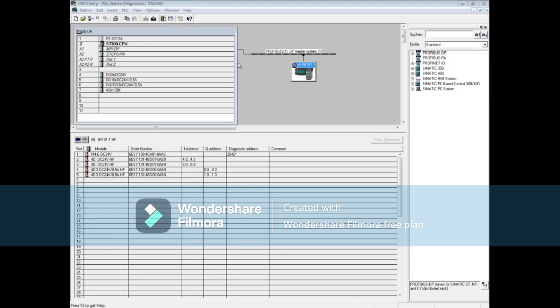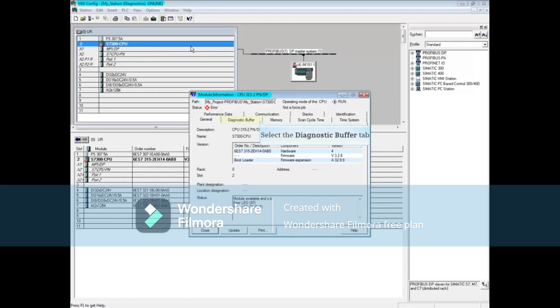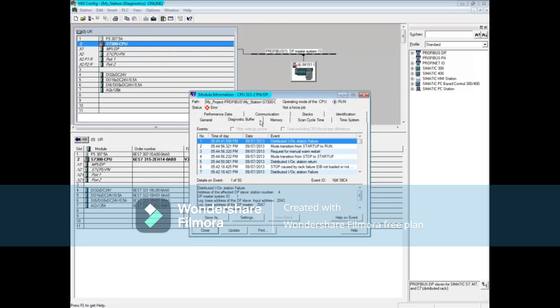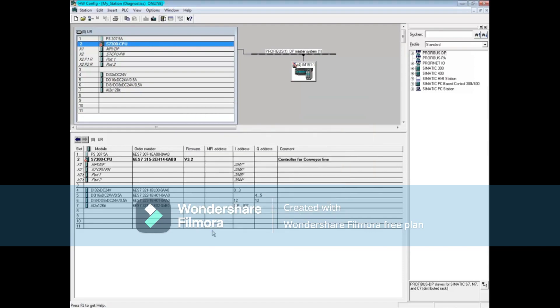Here is a second case scenario where the Profibus station is down like before, but this time OB86 was created and downloaded to the PLC. Double-click the CPU to open the Module Information Tool and click on the Diagnostic Buffer tab. Now you can see that the CPU is still in run mode because OB86 — the organization block that protects against rack failures — was downloaded. The first message shows that it is Station 4 that is down. When the problem is fixed, the station immediately comes back up and all faults are cleared without having to switch the CPU to stop and back to run.